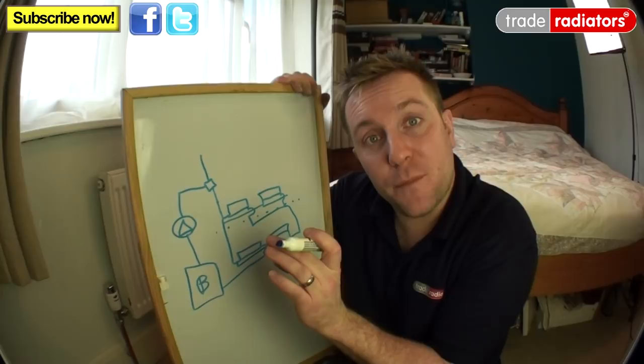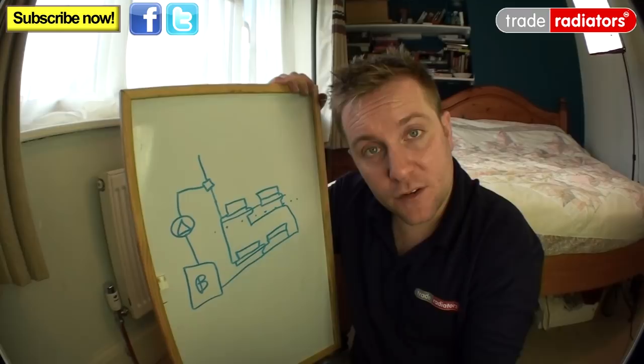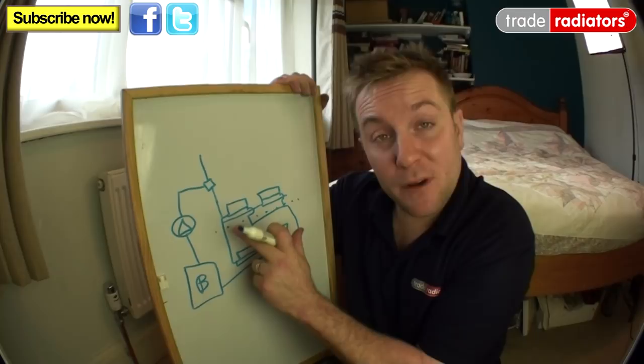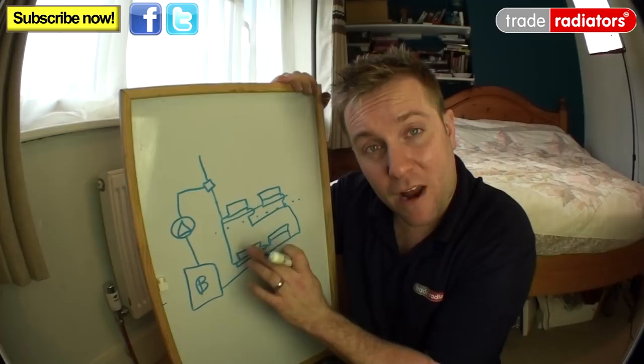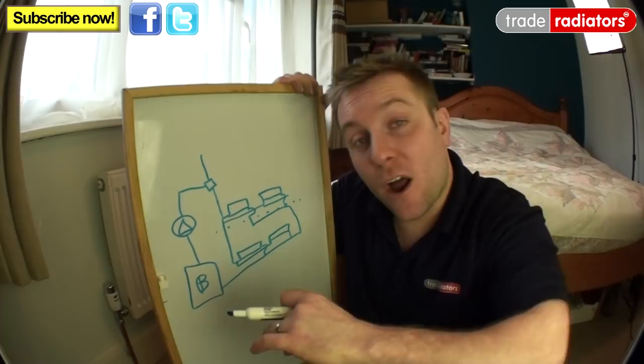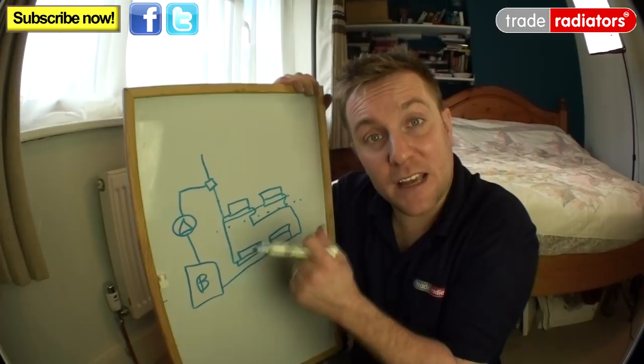What you'll notice then is that the radiator might take slightly longer to get warm, but not much, and it will always get to the hot temperature that it used to. What you've basically done is distributed the flow not just through that radiator, but pushed it to this radiator here more, and maybe these two at the ground floor. You'd then strangle this one down as well on the lock shield — shut it all the way down and open it back up half a turn — and then that one will be balanced. You should find that the two radiators downstairs are getting nice and warm.